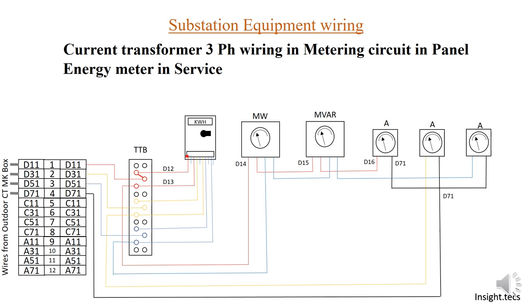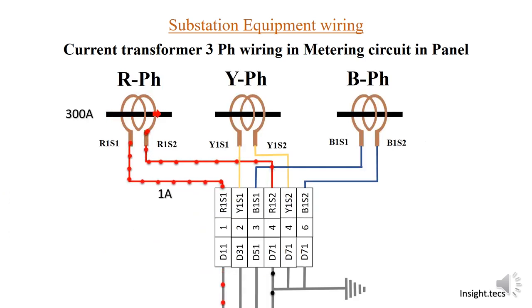When the energy meter is in service, the animation shows the current flow for R-phase; similarly you can understand for yellow and blue phase. Now let us understand how the current flows when the energy meter is out of service. Through the TTB, you can see that it is possible to bypass the energy meter when you want to perform any testing. The current flows from d11 and comes back into d71, and this animation shows how d11 comes into the panel and the current flows through the circuit and returns as d71.